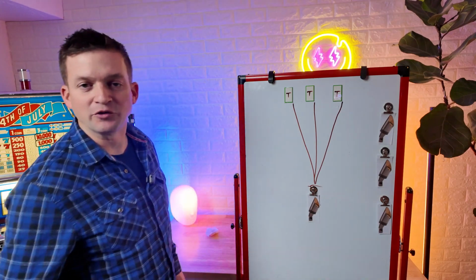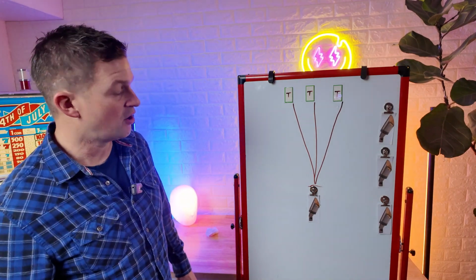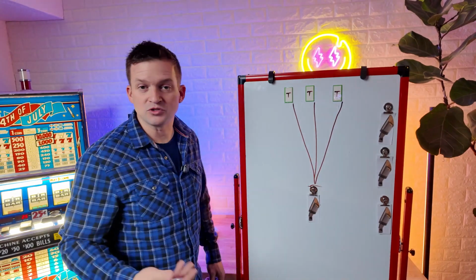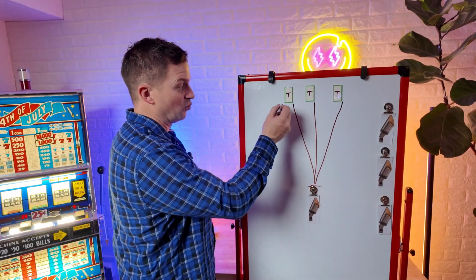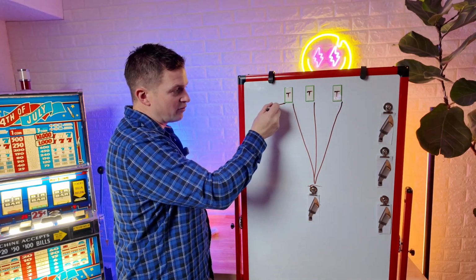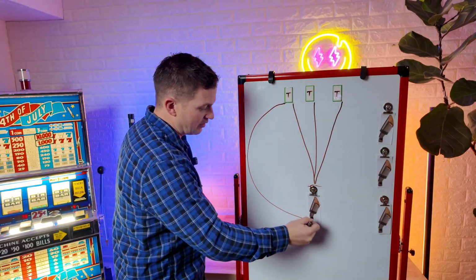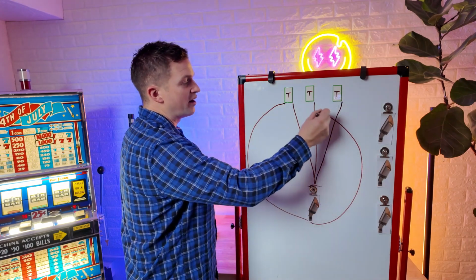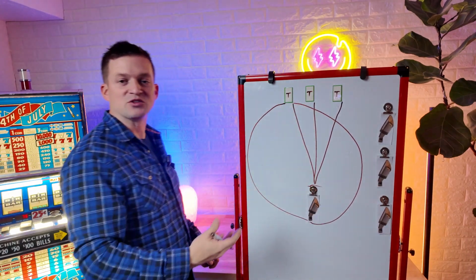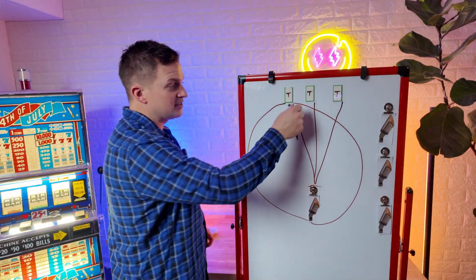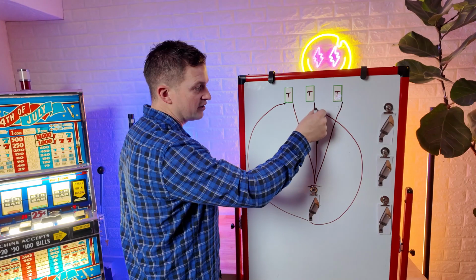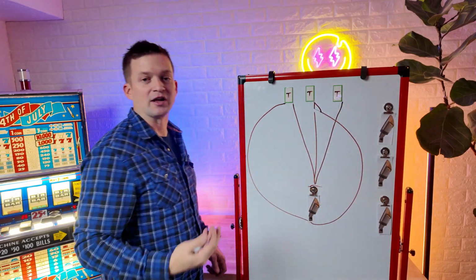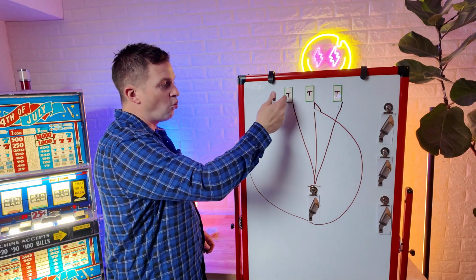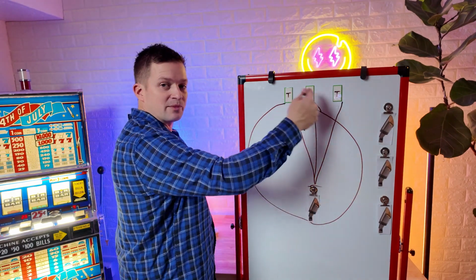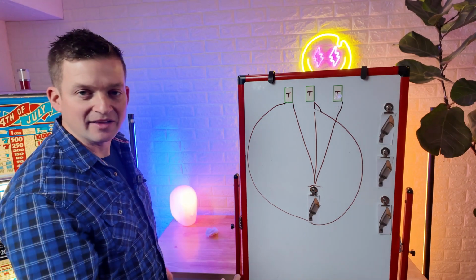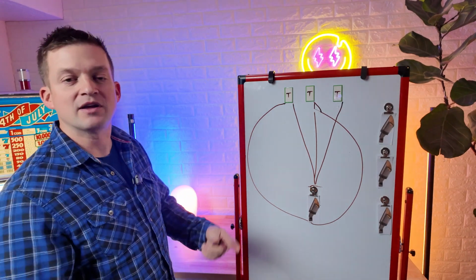This could have happened inadvertently through repairs through the life of the system, or it could have happened if originally the system was installed perhaps with a loop method that used to be popular, where you would have wiring from one transformer that would connect to a fixture, and then you would run that wiring back to the same transformer. But because we've got 3 transformers adjacent to each other, it's conceivable that maybe the other side of the wire at some point got ran back into a different transformer. Now you would have one wiring loop connected into 2 separate transformers, and as long as the polarity and the voltage conductor aren't crossed, it would never trip the breaker.